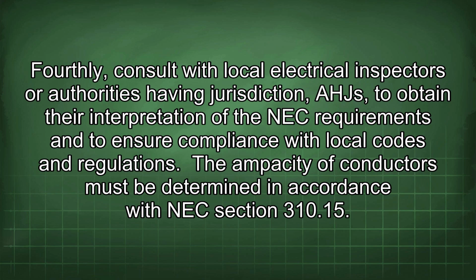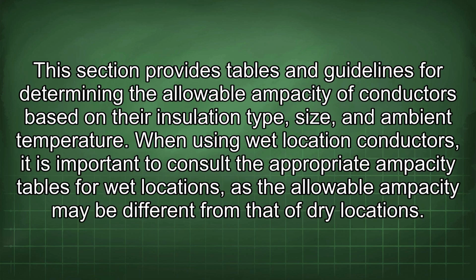The ampacity of conductors must be determined in accordance with NEC section 310.15. This section provides tables and guidelines for determining the allowable ampacity of conductors based on their insulation type, size, and ambient temperature. When using wet location conductors, it is important to consult the appropriate ampacity tables for wet locations, as the allowable ampacity may be different from that of dry locations.